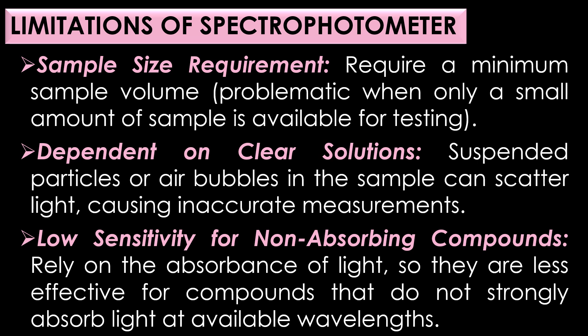The seventh limitation is dependent on clear solutions — suspended particles or air bubbles in the sample can scatter light, causing inaccurate measurements; therefore sample clarity is critical for accuracy. The final and eighth limitation is low sensitivity for non-absorbing compounds — spectrophotometers rely on the absorbance of light, so they are less effective for compounds that do not strongly absorb light at available wavelengths.